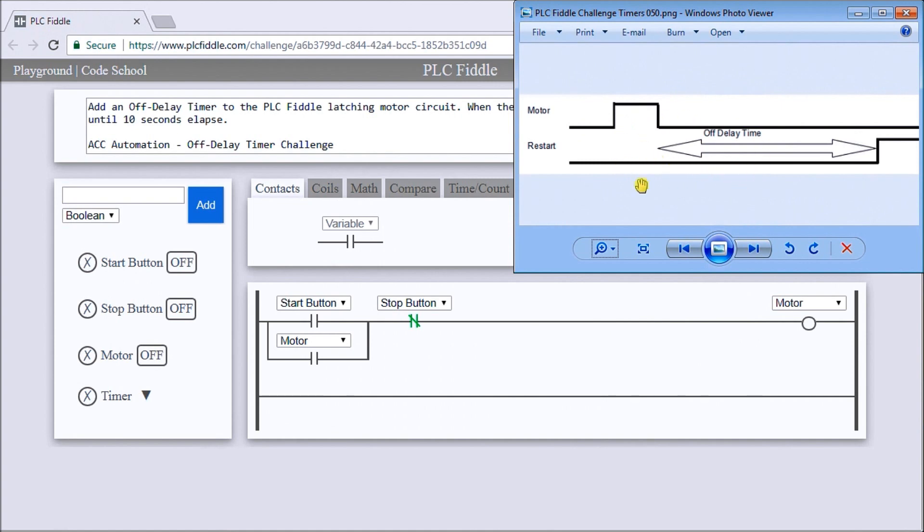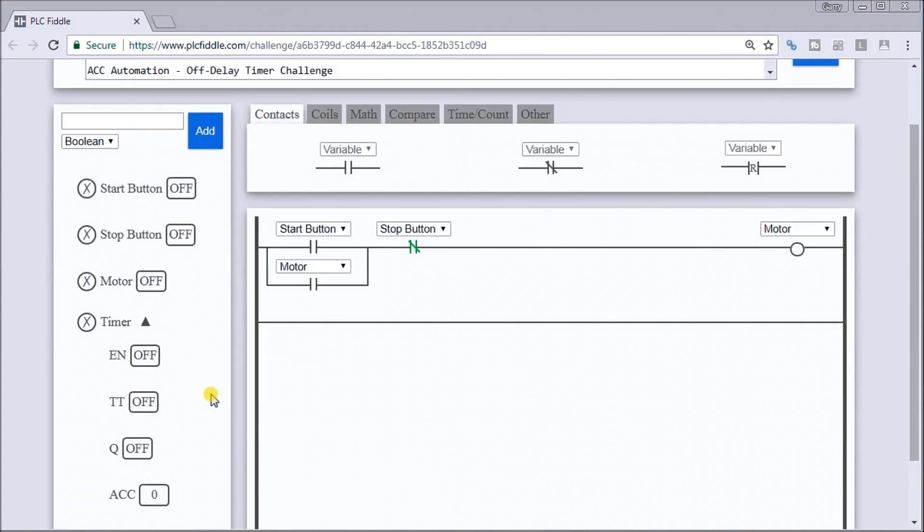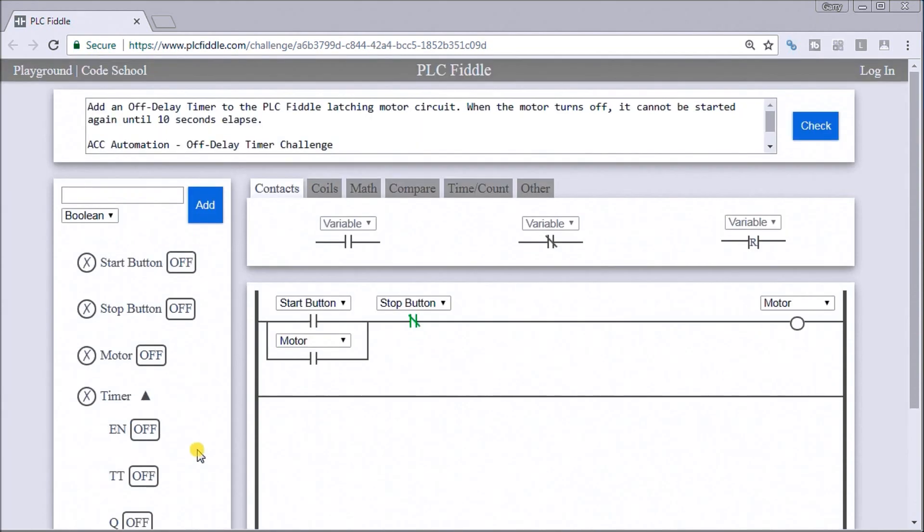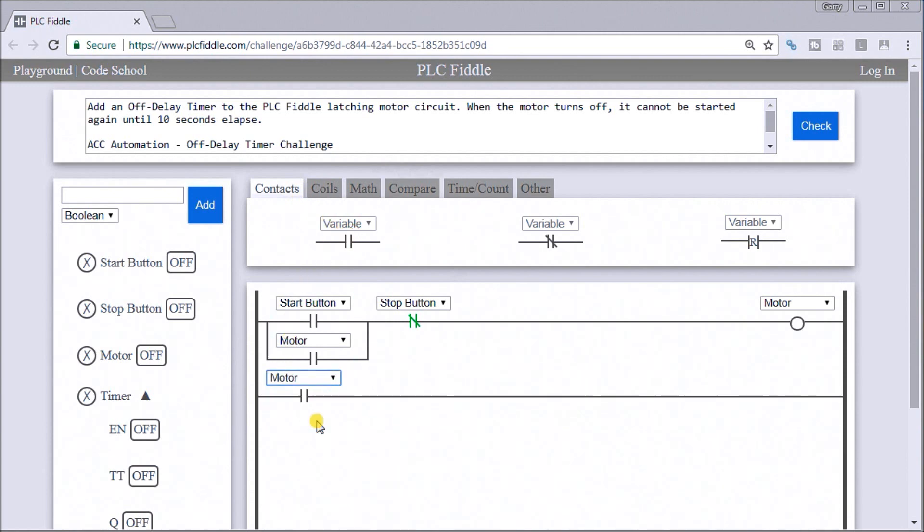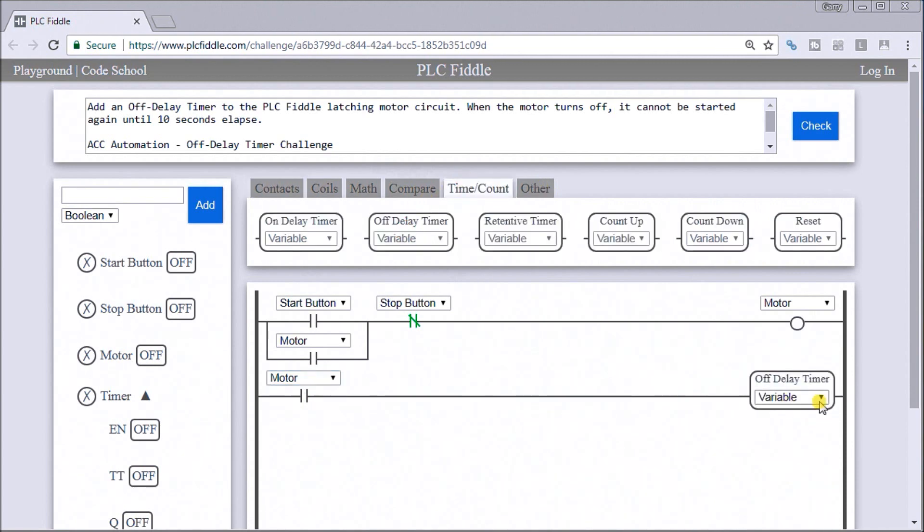Let's look at our program. We have just a timer instruction here. You see it's set for 10 seconds for our preset value. Let's go to our motor itself. We'll go to a contact here, put this on the rung and say that's the motor. Then we'll go to an off-delay timer which is right here.